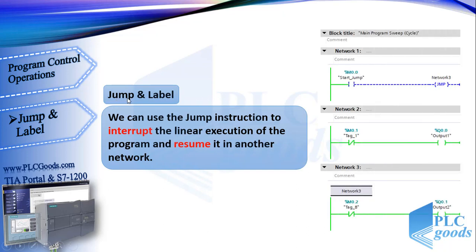The first is jump and label. We can use the jump instruction to interrupt the linear execution of the program and resume it in another network. Let's see what this instruction does in this program. Here we have three networks. In the first network, a jump instruction is used which refers to Network 3.